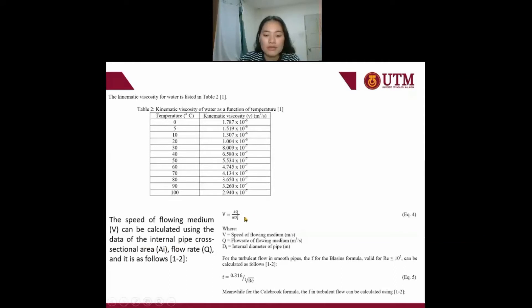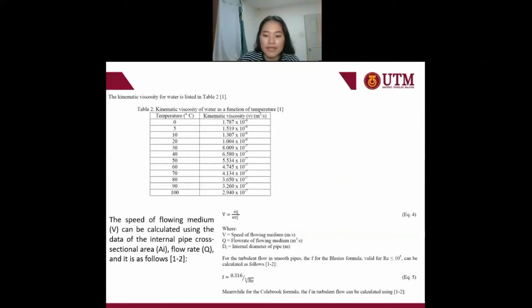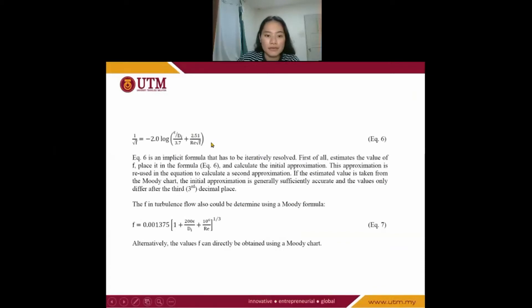Speed is equal to 4 times the flow rate of the flowing medium, divided by pi multiplied by the internal diameter squared. For turbulent flow, the friction factor using the Blasius formula, valid for Reynolds numbers lower than 10⁵, can be calculated using this equation. Meanwhile, for the Colebrook formula, the friction factor for turbulent flow can be calculated using this formula.